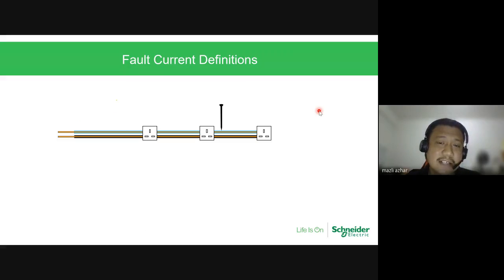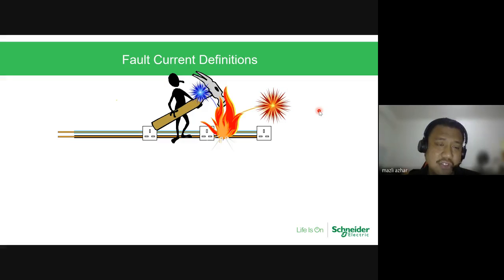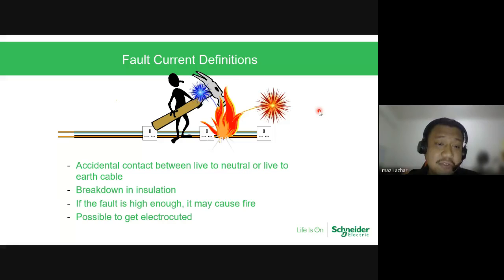Okay, so take an example, very simple. You have a 3-pin socket. Normally in installations in Malaysia, they will use a ring circuit, whereby each one from an MCB goes directly to the 3-pin socket, and then everything is installed inside the wall, so you can't see where the cable is running. So take an example, one day you want to hang something on the wall, then you accidentally touch live and neutral, or live to earth cable, which is caused by a breakdown in insulation. And if the fault is high enough, it can cause fire due to the spark created when there is a short circuit, and it's possible for you to get electrocuted, something that you want to avoid in your entire life.